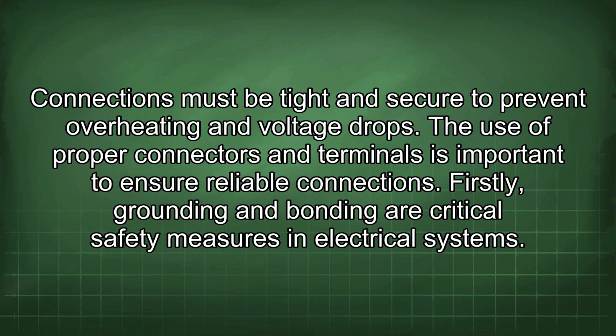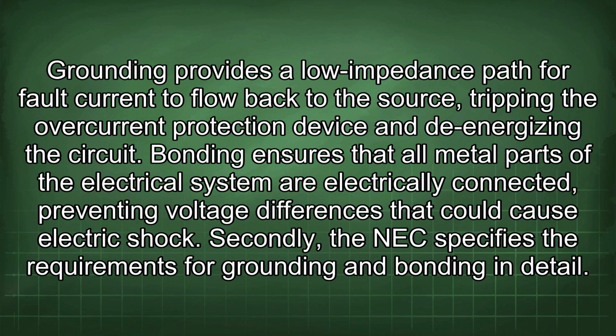Firstly, grounding and bonding are critical safety measures in electrical systems. Grounding provides a low impedance path for fault current to flow back to the source, tripping the overcurrent protection device and de-energizing the circuit. Bonding ensures that all metal parts of the electrical system are electrically connected, preventing voltage differences that could cause electric shock.